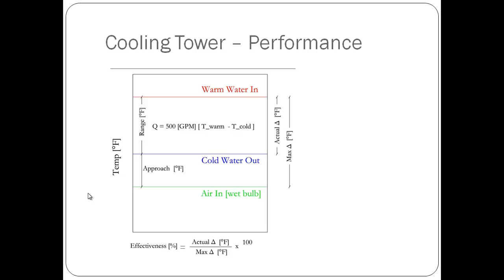The range of the cooling tower is the difference between the entering and exiting temperature of the cooling tower water. The approach, or approach to wet bulb, is the temperature difference between the water out and the wet bulb temperature of the air. The approach is important because it describes the level of performance of the cooling tower.